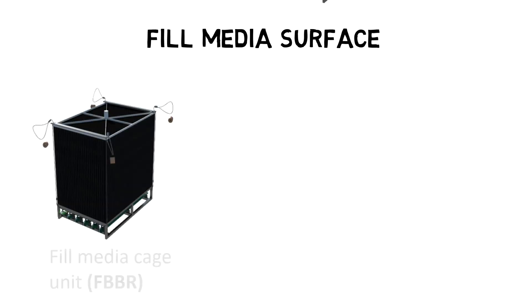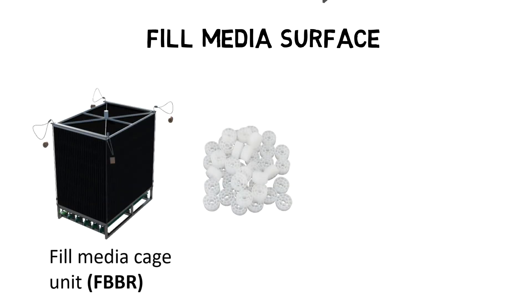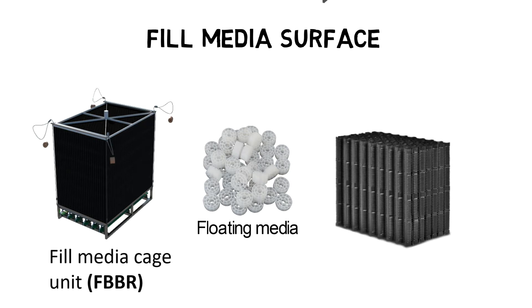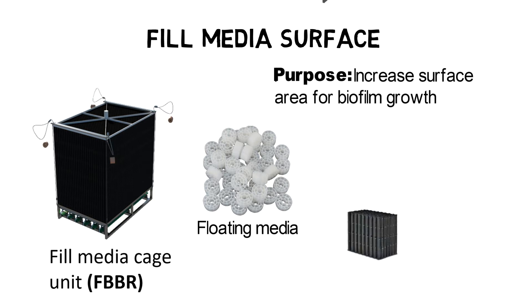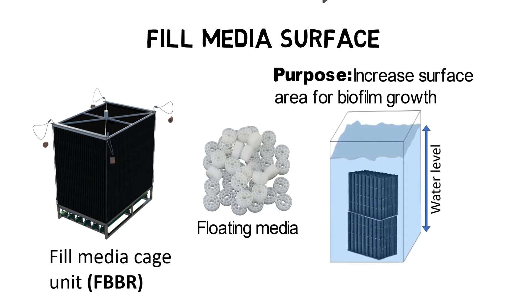The fill media can either be added to the aeration tank as free-floating chips or in the form of retrievable fill media cage units. In both cases, the fill media fulfills the same purpose: to provide additional surface area within the aeration tank for attached biofilm growth. The available surface area per fill media block could be up to 70 square feet (220 square meters), so that depending on the water level, the tank base area can be increased more than 500 times.